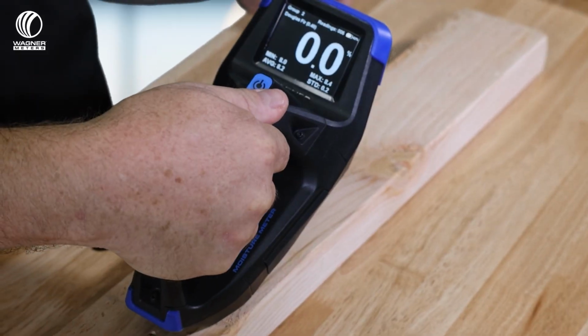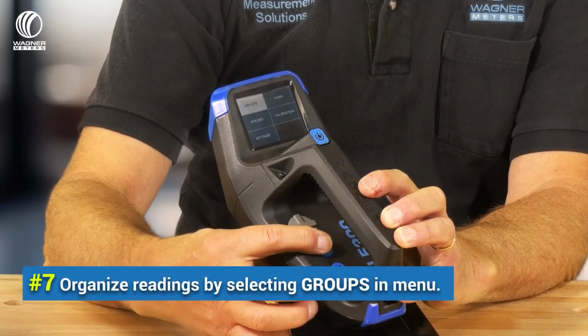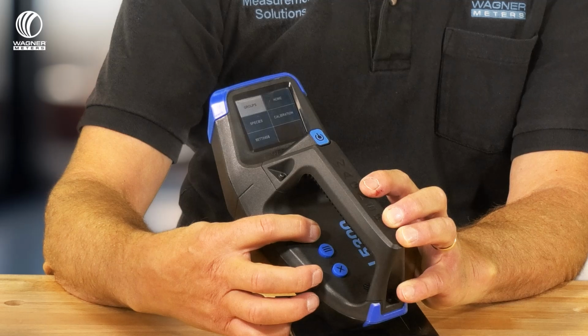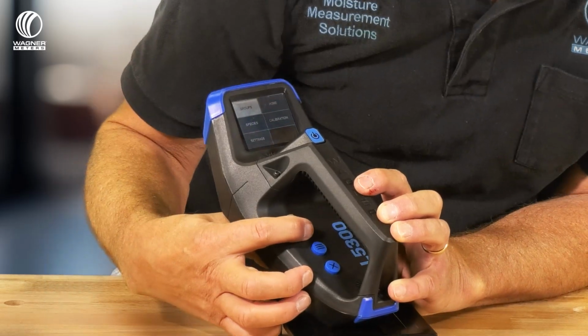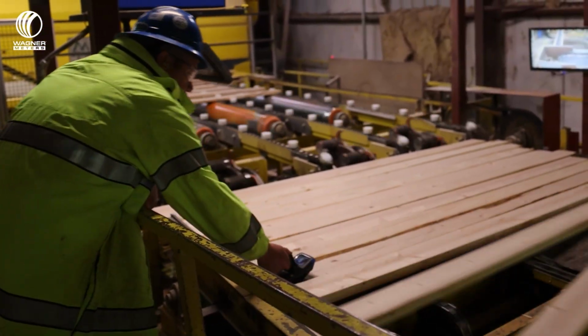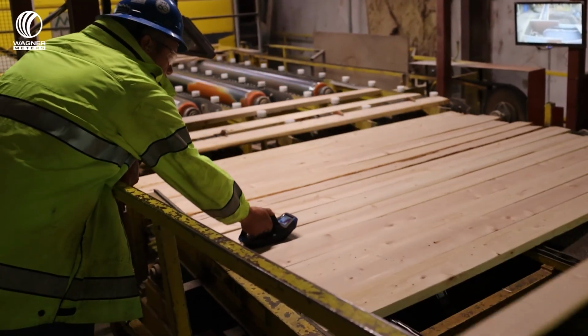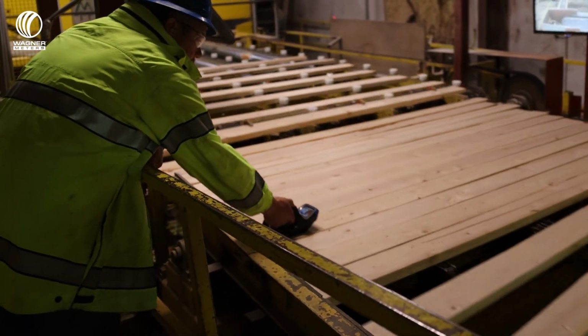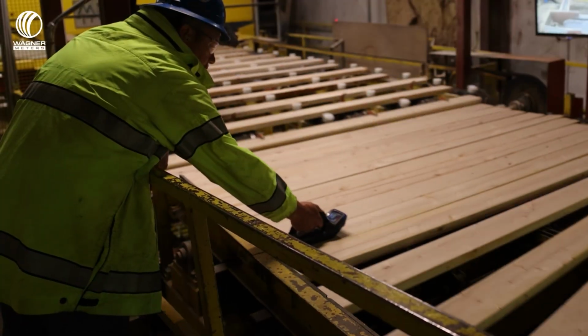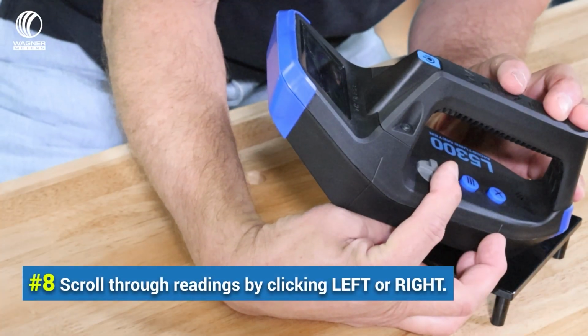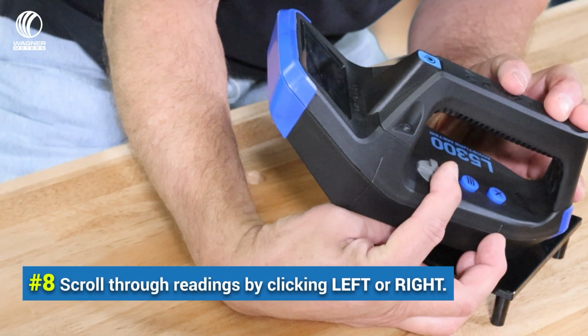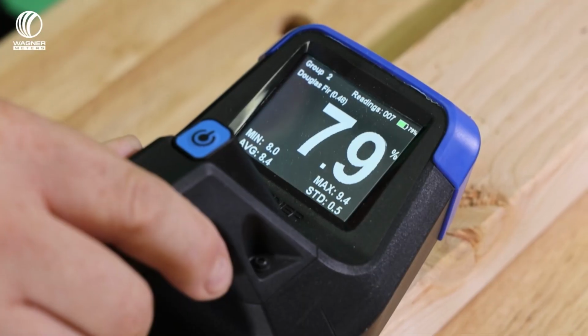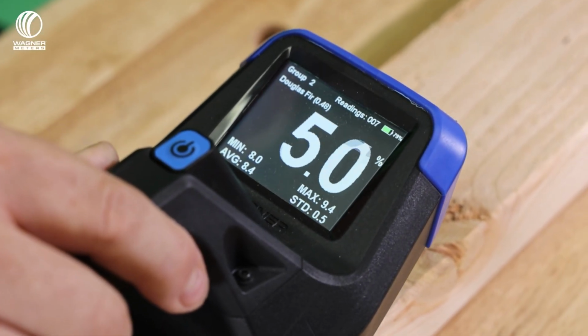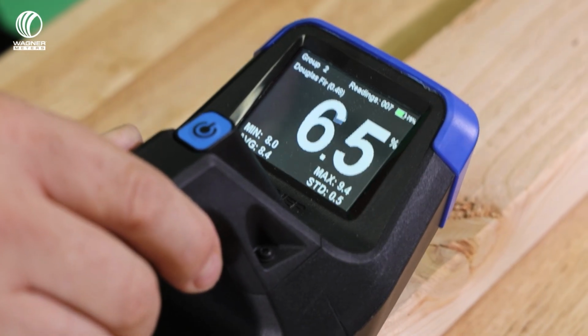If you want to organize your readings, go to the Groups menu and select a specific group before taking measurements. This feature helps you track readings for specific areas, such as kilns or different sections of your lumberyard. To view stored readings and statistics for different groups, use the left and right buttons on the jog pad to scroll through them. Here you will see each group's minimum, maximum, average, and standard deviation of moisture content.